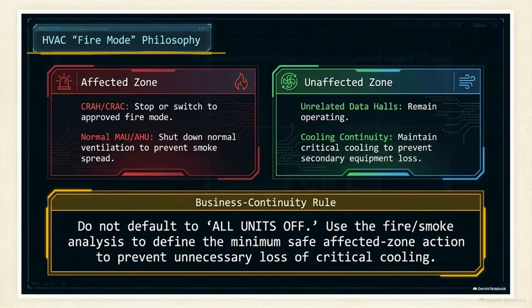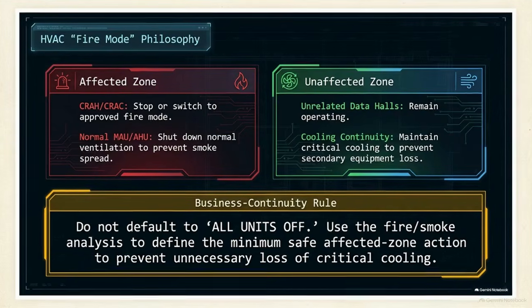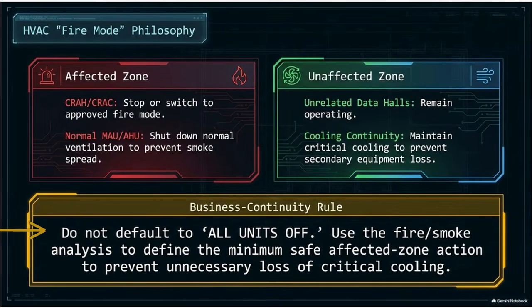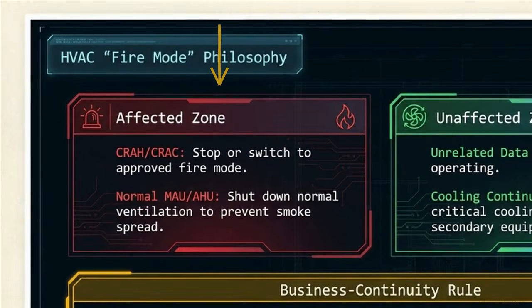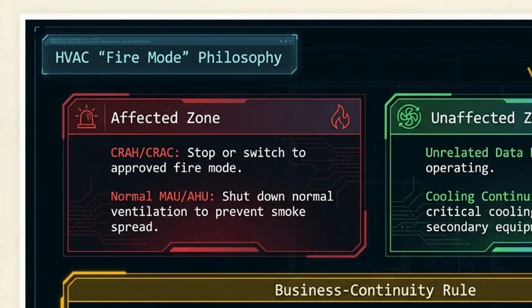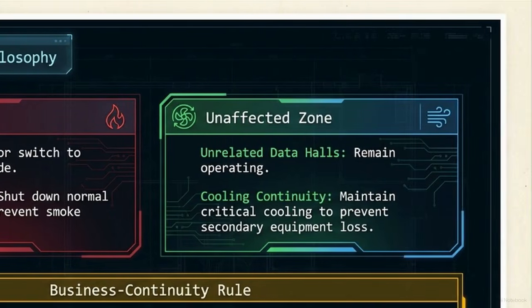This HVAC philosophy chart details how the matrix commands cooling systems during an event. Data centers explicitly reject the traditional default of shutting all air units off during a fire alarm. The business continuity rule demands that while the affected zone isolates to prevent smoke spread, unaffected data halls must remain operating. Maintaining critical cooling in those adjacent zones prevents massive secondary equipment loss.